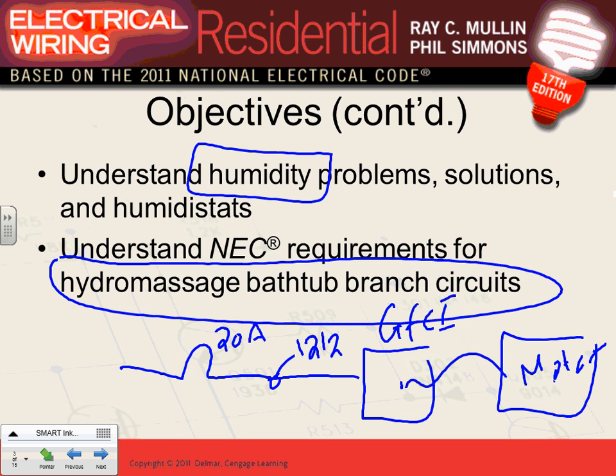All the control, what happened to the control? The control is all built into the hydromassage bathtub motor. It comes with push buttons that you use to start and stop. Can I have thumbs up, Chad? We understand how this hydromassage bathtub goes. 20 amp circuit, 12-2 to a GFCI receptacle, plugged in. The only thing that they say, all GFCIs right now as of 2011, and this has been true even before 2011, they have to be readily accessible.